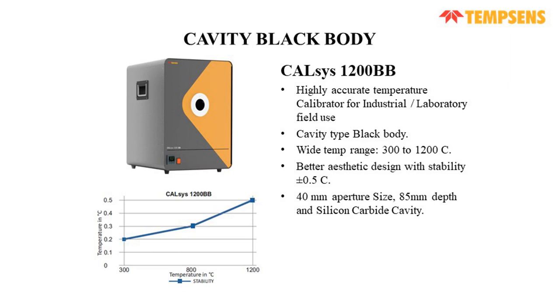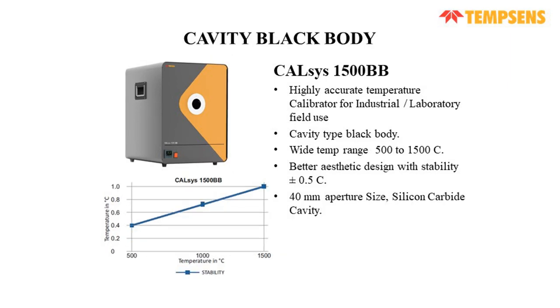It has a silicon carbide cavity, and the temperature range for this model is 300 to 1200 degrees centigrade, with a stability of plus minus 0.5 degrees centigrade. It has an aperture size of 40 and a depth of 85. The immersion depth of the cavity will be around 85, and the cavity is silicon carbide. This is the 1500 BB, again a cavity type black body. The temperature range is 500 to 1500 degrees centigrade with a stability of 0.5 degrees centigrade. It also has a 40 aperture size and a silicon carbide cavity.